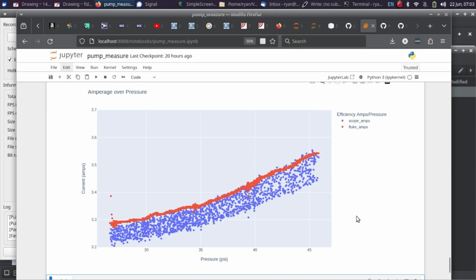Other things I could look into with this are if I move the pressure tank precharge up from 30 to run in the 30 to 50 psi range, then I can look at whether the pump does better there. From what I found, we don't get more tank capacity out of the higher pressure range - it just makes the outlet stream a little more forceful, which might be useful for sprinklers or soaker hoses. But I don't really want to run this pump at a higher range than necessary, especially because we're already going from 3.3 to 3.5 amps. The pump motor, I think, says it's rated for 3 amps full load amps, so it might already be drawing a little more current due to its age and operating condition. I don't see any need to push an older pump like this higher and risk damaging it.